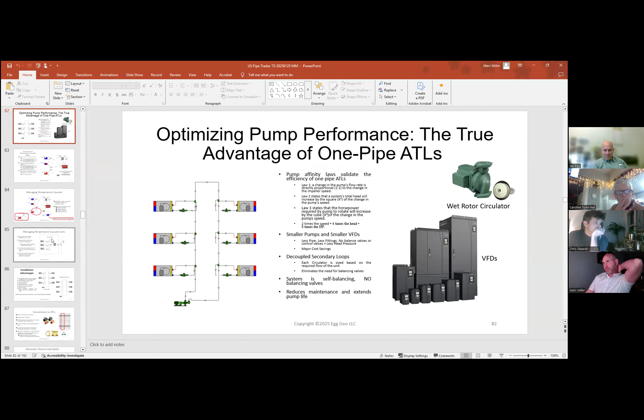So what we have here is a one-pipe system. ATL isn't Atlanta, it stands for ambient temperature loop. We have our geothermal loop here, an example of a closed loop, targeting a 75-degree inlet temperature. Keep in mind this is all theoretical for demonstration purposes. We go into a heat exchanger here at 75 degrees, and whether it's heating or cooling season will determine what the discharge temperature is going to be.